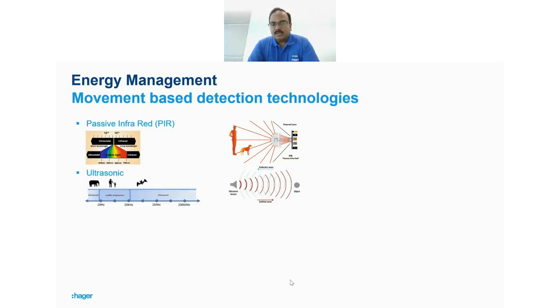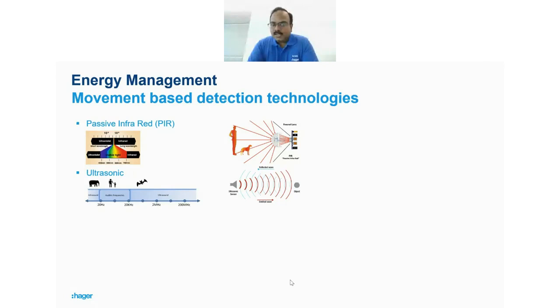The next technology used for motion detection is ultrasonic, which is based on sound. The PIR is passive because the device doesn't generate any IR — it waits for radiation to reach the sensor. Ultrasonic is the opposite: the device continuously sends a sound wave, and once it hits an object and returns as a reflection, it knows something has moved or a new pattern has been created.